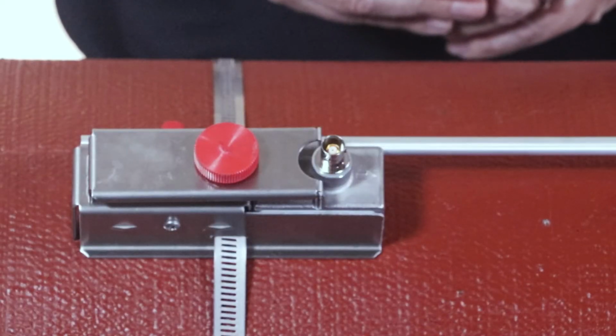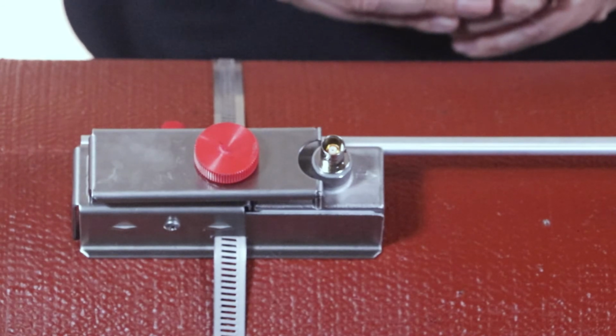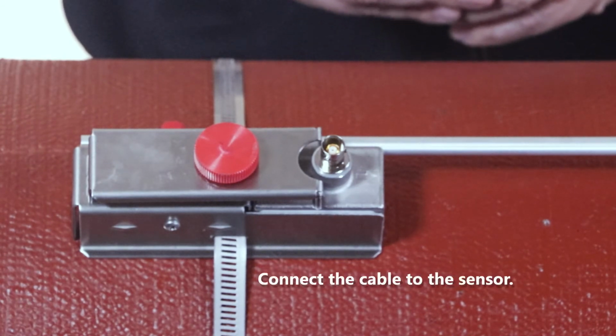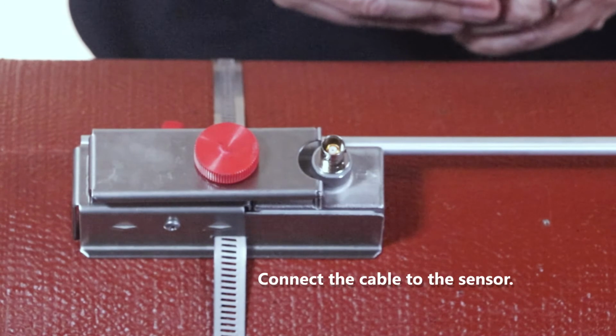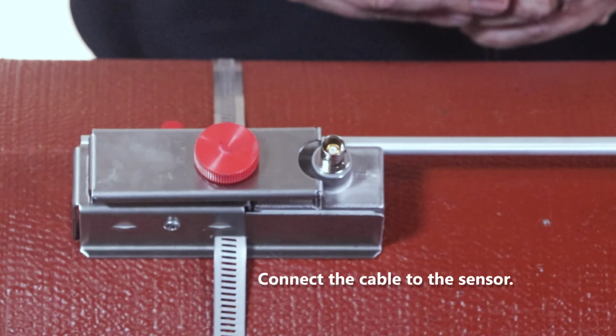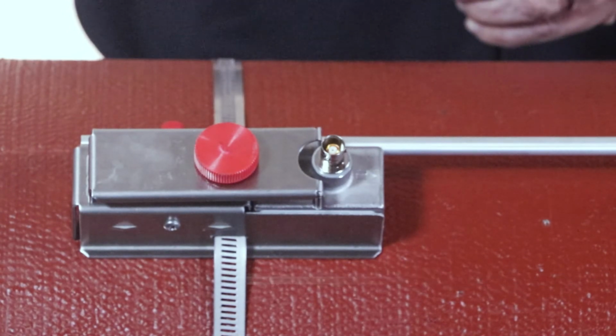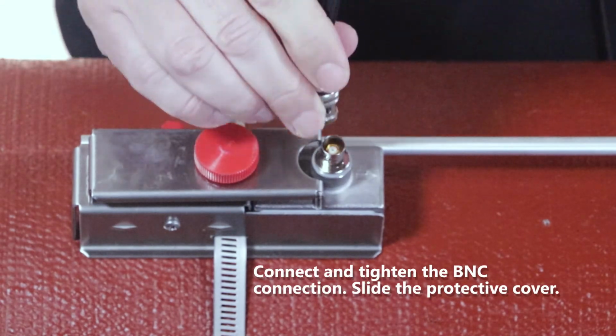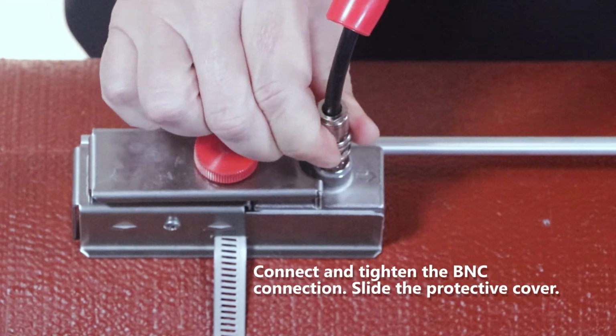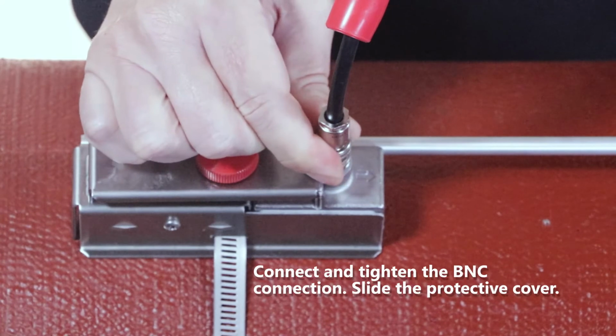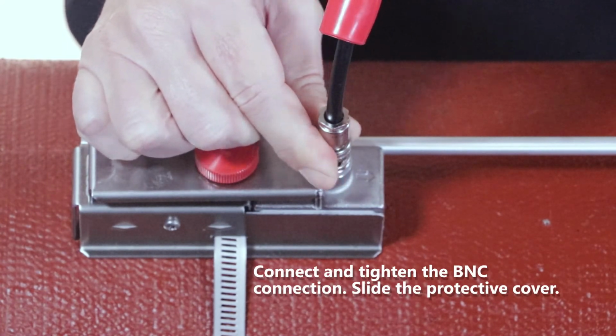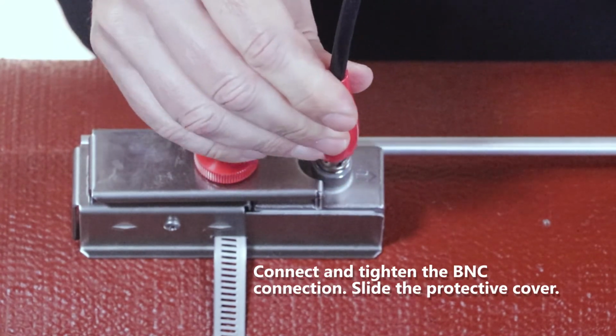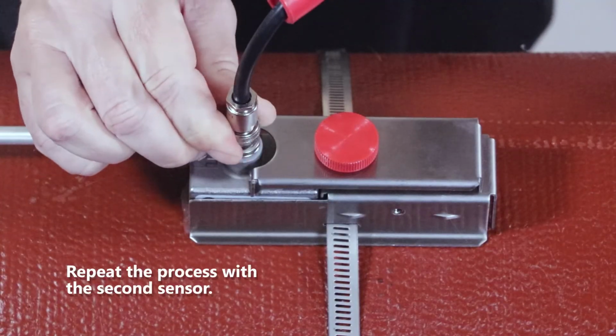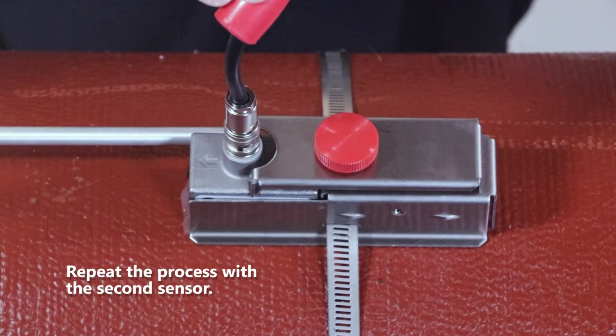The final step in the installation of the transit time flow meter is to connect the cable to the transducer. Remember, in our scenario, flow was moving from my right to left. We'll use the upstream cable on the right transducer and connect with the BNC connector. Once the connector is on, we'll slide the protective cover on top of it. We'll repeat the process with the downstream transducer.